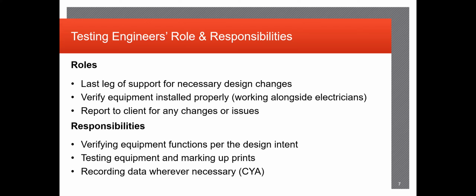Usually this will be done with highlighting the prints to not only show that it has been tested, but to verify that if you were to go back and going along this next line, recording data, to be able to go back after the equipment is placed in service to prove to our client and whomever else that the equipment was tested and functionally verified prior to place in service. Anything like that.